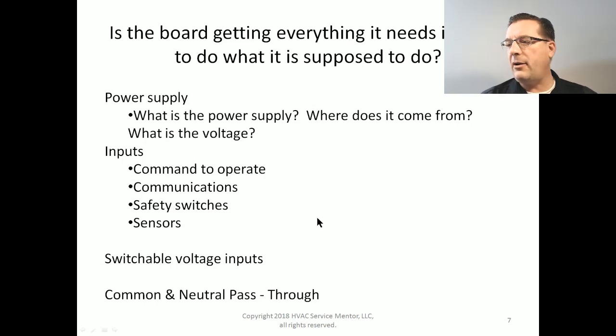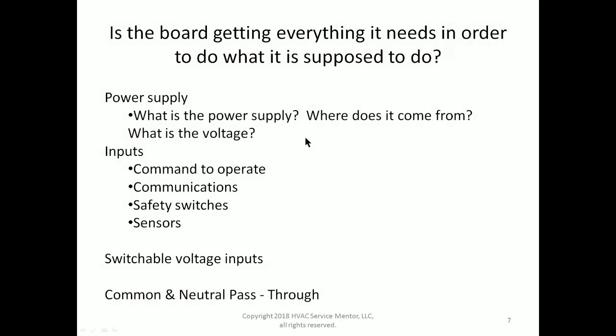Once we have identified that, yes, in fact, the fault code is happening, or there is a fault, the next thing we need to figure out is whether the control board is getting everything that it needs in order to do what it's supposed to do. Imagine this example. We have a control board and it's not doing something. We've identified that it's not doing X. Say it's not energizing the draft inducer, or it's not energizing the blower. The next question we need to ask and answer is, is the board getting everything that it needs in order to do what it's supposed to do? Beginning with the power supply, we want to identify what the power supply for the control board is, where it comes from, and what voltage it is. Then we follow up with, is it there where it's supposed to be or not?